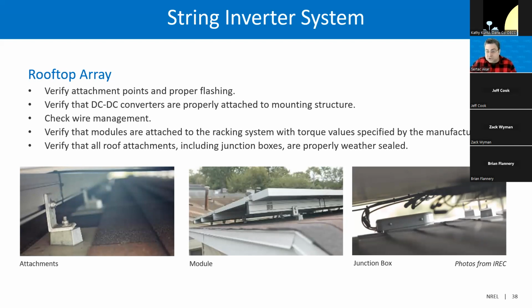The main things to check at a rooftop array are modules, attachments, junction boxes, and also wire management. All roof attachments, including junction boxes, must be properly weather sealed. DC-DC converters must be properly attached to the mounting structure, and the modules must be attached to the racking system with torque values specified by the manufacturer.